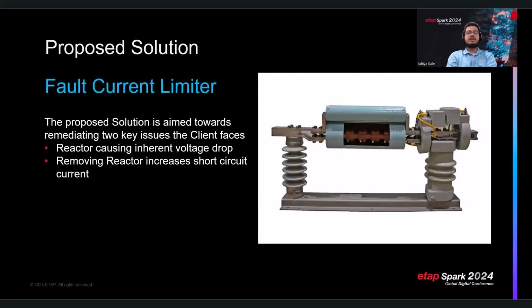Given the challenges, our proposed solution directly addresses the 2 critical issues. One, the existing reactor causes a significant voltage drop, which is further exacerbated when starting large motors. And two, removing the reactor reduces this voltage drop but significantly increases the short circuit current. This scenario creates an opportunity for a solution like adding the fault current limiter FCL, also known as a triggered current limiter TCL.